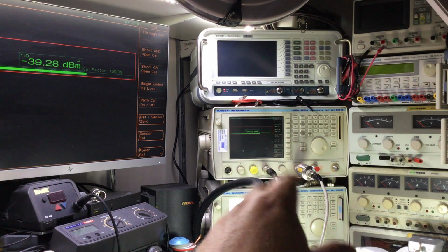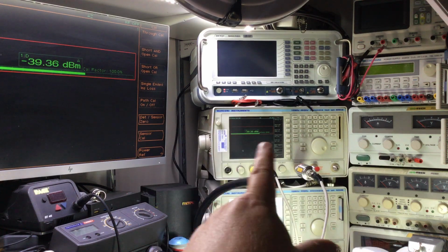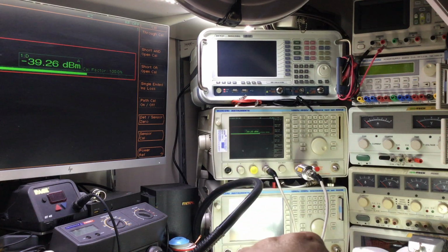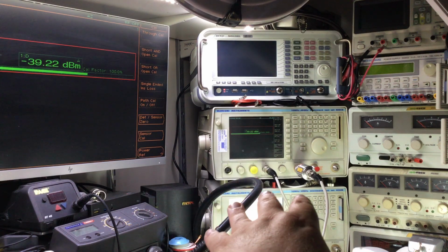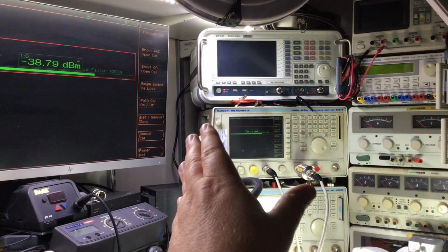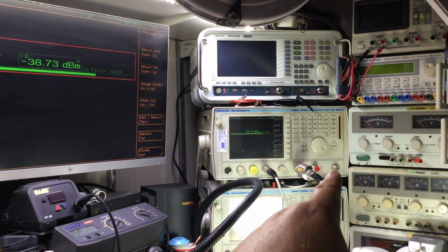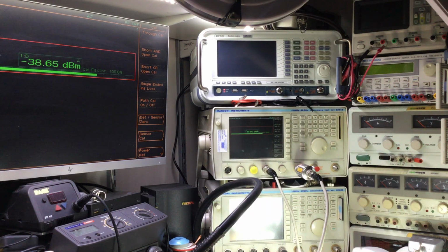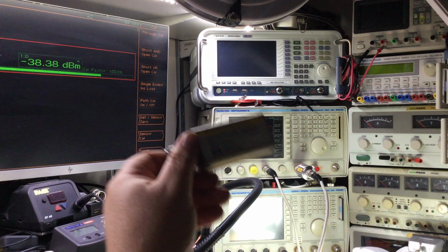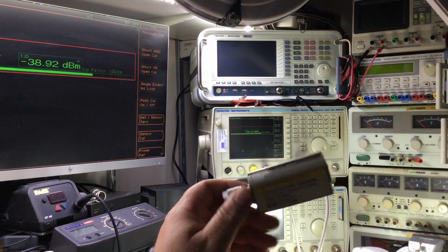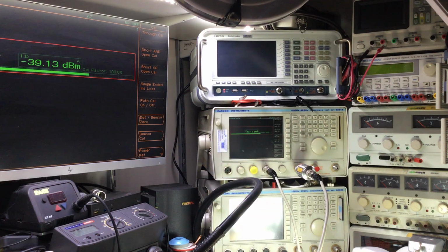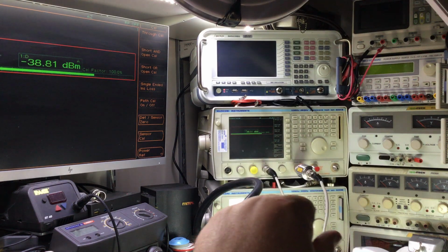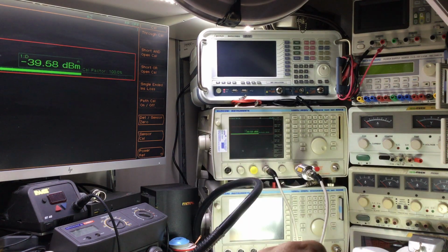So we're going to be using this as a frequency sweep at 0 dBm, and we're going to check the sensors on the HP meter read correctly up to 26.5 gigahertz, which is the sensors' usable frequency range. So we're going to be using that test set for that particular test number 2.